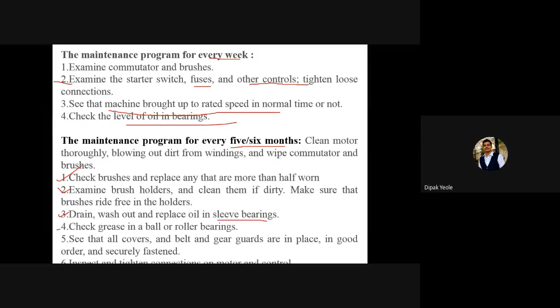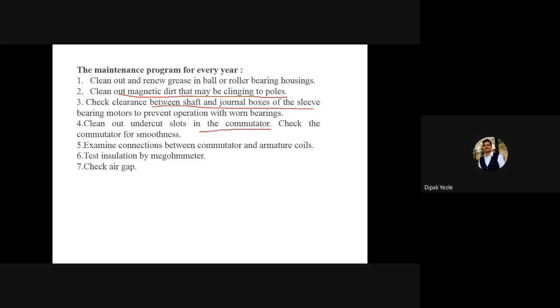We have to clean out and renew the grease in the ball bearings. We have to clean out magnetic dirt that may be clinging to the poles. Magnetic dirt sometimes collects on the magnetic poles, so we have to clean it. We have to check the clearance between the shaft and journal boxes of the sleeve, and clean out the undercut slots in the commutator. We have to examine the connections between the commutator and armature coils. We have to test the insulation with the help of a megohmmeter, and we have to check the important air gap after every year.